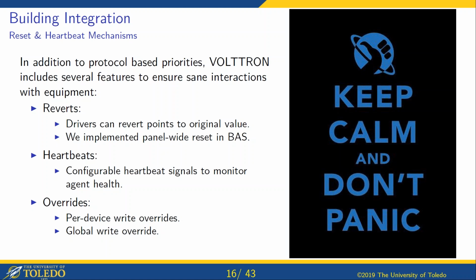Dave, let me interject for all the facilities people out there right now. This slide is important, more than the Douglas Adams reference on the side. When Dave's talking about VOLTTRON, it's on top of your automation, whatever you've got in your existing system. And the heartbeat is critical so that it's only going to control the set points that are out there. And it's working back and forth amongst the individual devices, changing those set points for that transactive piece. But if it ever had a problem, that heartbeat, the signal coming back, would put it all back under automated, whatever the logic system that you've already got in place, and your occupants wouldn't see a difference at their end.